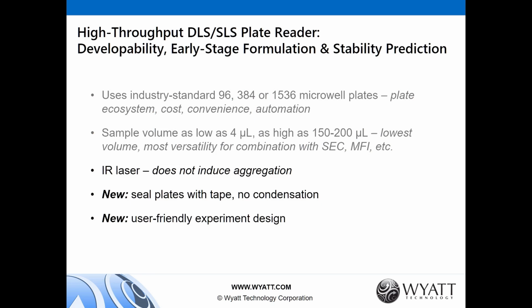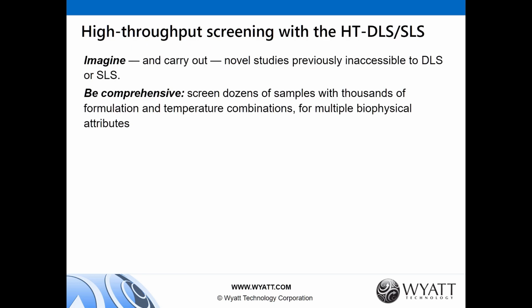The IR laser, 830 nanometers, there's no risk of it inducing aggregation. And new in the plate reader, we offer plate sealing using tape without condensation. I haven't shown it, but the software also offers a new user-friendly experiment design so that you can, in very short time, generate the standard methods that you're going to use to run through all these formulations and candidates.